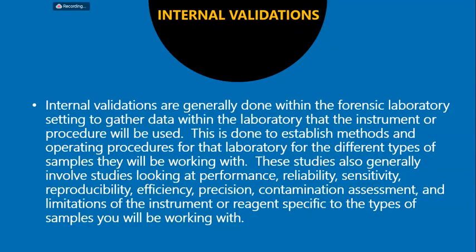So each lab should do their own studies on all the documentation in their lab, and this will help you with your DNA interpretation once you get your results. Knowing how all of that equipment is working in your own settings will help you when working with all different kinds of samples, but specifically trace samples. So in these studies, for each different part of this study, you can create known samples with known mixtures, with a varying number of people involved in the mixture, different amounts, and then you look at that data to see what the profiles look like with things that you know what should be there. That helps you see if you're missing information, see if you have issues, if the instrument or the process is working how you expect it to, things like that.